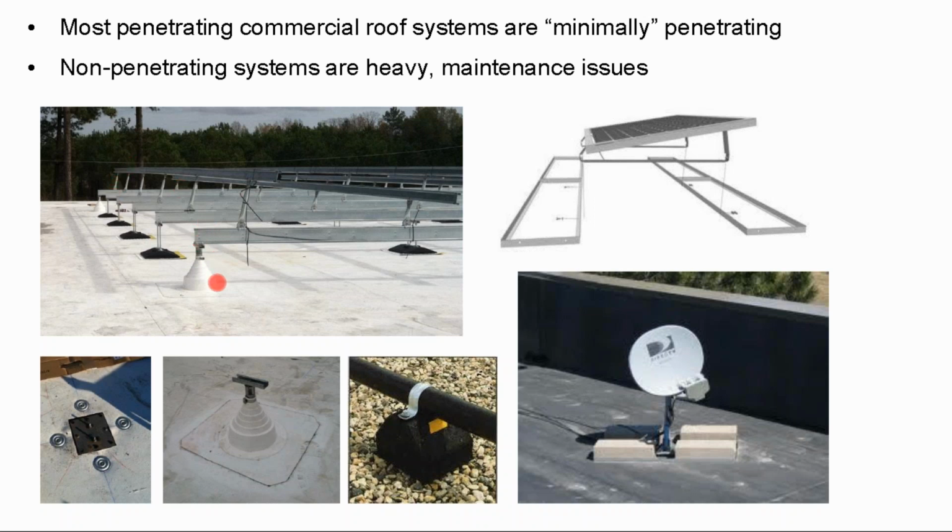And it turns out, you either need to use a lot of weight to overcome that friction coefficient, or you can secure it to the rafter to overcome that friction coefficient. One way requires a lot of weight, the other one doesn't. And so the point is, in your commercial designs, consider using an installer who can poke a hole in the roof and seal it in a competent manner. And that might mean you use a combination of a roofing crew and an electrical crew for the install.